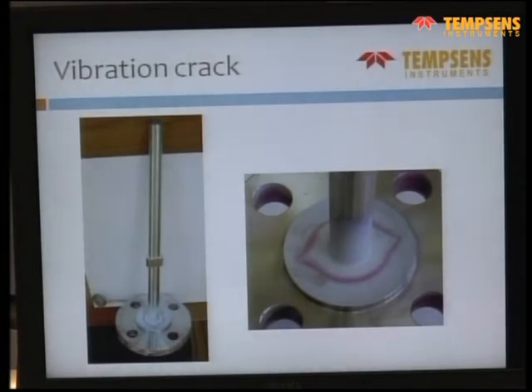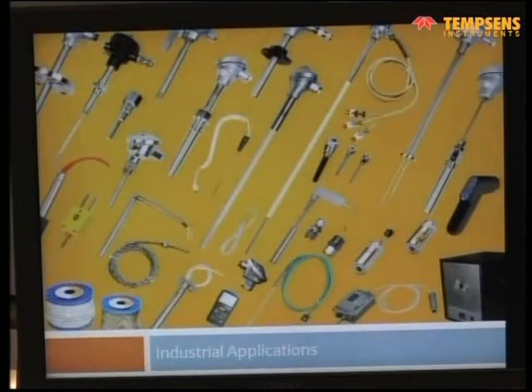These are typical vibration cracks that we have seen when thermowells were put into use. Within a short span of time we had this issue of vibration cracks, when the calculations were not properly done, or when they thought the flow would be a certain amount and it was actually different than what was envisaged. So that's about thermowells. If you have any questions, you can ask, or maybe we can proceed.